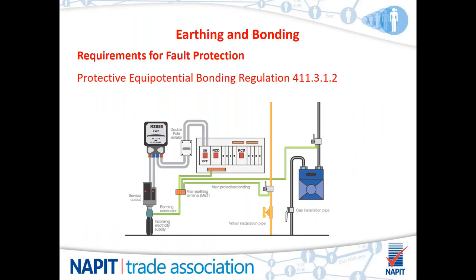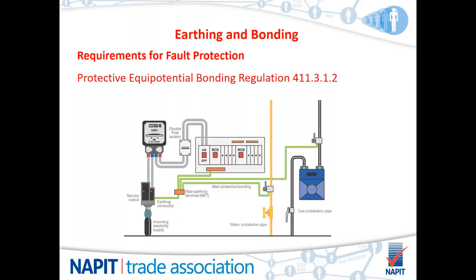So in the diagram you can see on the screen now, it demonstrates a TNS system and methods for bonding and earthing. Now, on a TNS system, it's obviously identifiable as the main earth comes off the sheath from the incoming cable. And this one is the modern day PME system, TNCS system, where the supply neutral becomes the earth at the service cutout. You can see that the earthing conductor is in the neutral block at the service cutout head. This should only be performed by the DNO.